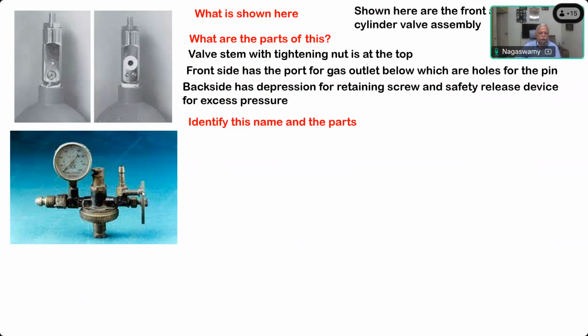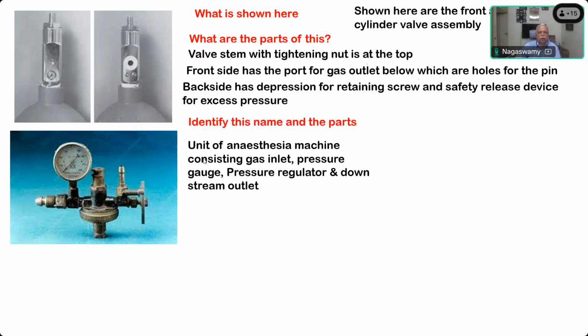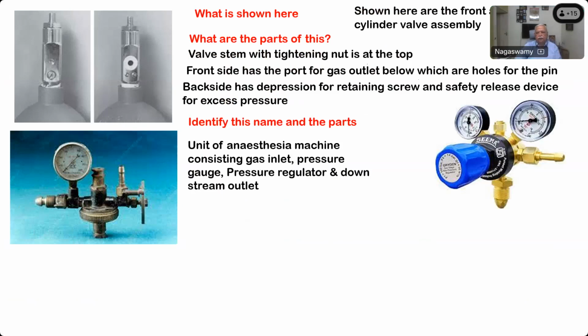The oxygen flush or the oxygen fail-safe alarm. So two connections will go from the pressure regulator. One will go to the flow meter. This is a unit of the anesthesia machine which consists of gas inlet, pressure gauge, pressure regulator, and downstream outlet. This portion is the downstream that is going to the flow meter or the emergency oxygen flush and other things.